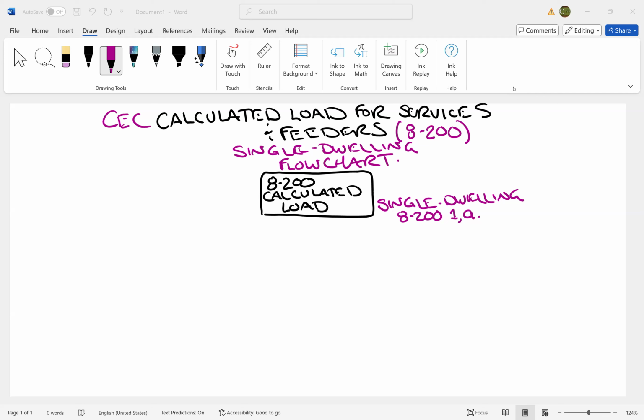Now, going down the heating section, we have to ask what type of heating it is. Is it electric thermal, duct heaters, or electric furnaces? If so, you have to go out of section 8 of the electrical code and go to the specialty section 62, rule 62-118, for this calculation.